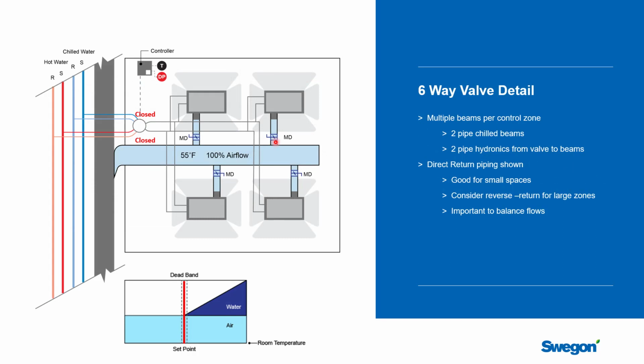So let's look at how one would be piped in. We said it would be a 4-pipe system, so you've got a hot water and a chilled water loop. Here's the 6-way valve. Right now we're neutral, so we'd be at about 5 volts on that control sequence. The valve would be sitting in the middle, not allowing either hot water or chilled water to get out to the beams. And you can see why they're so popular.